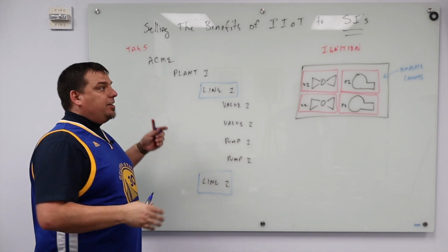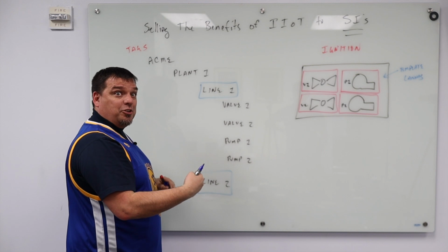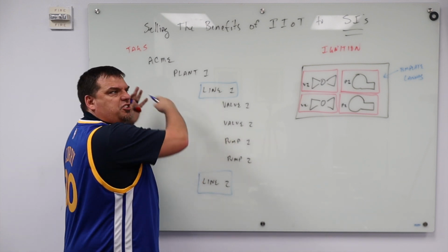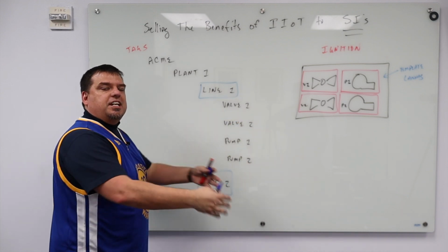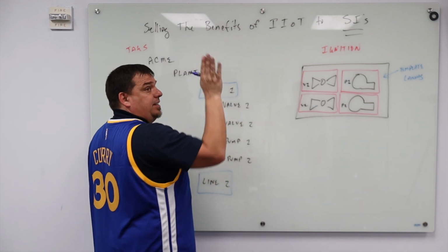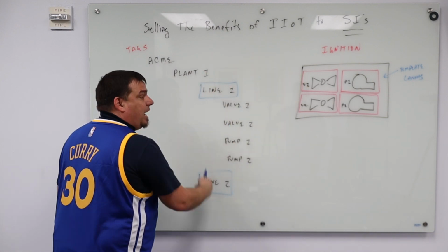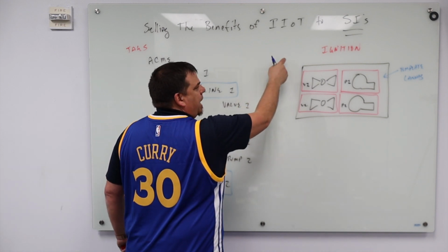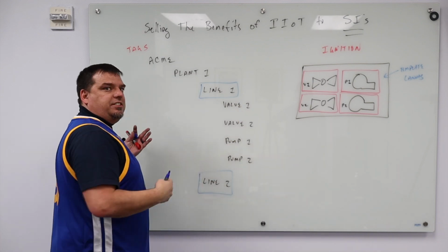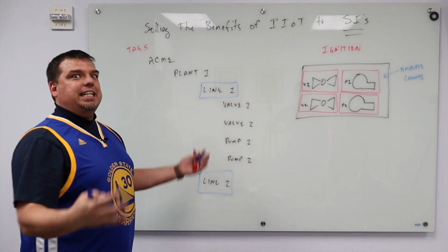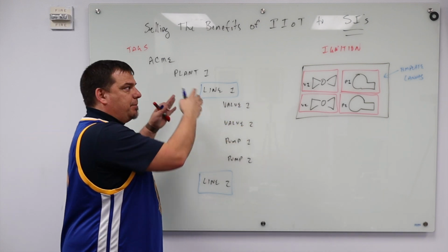In the old days, you had to have your OPC server point to this PLC. You have to build all your tags in your OPC server, and then they'll be here. There's a ton of engineering that goes into just getting the line and all the tags in. What MQTT does is it takes all that away. Here's the other thing. In the old way, your screens have to know what all the tags are that exist already. How many lines do you already have? Because you're going to statically bind, if this is an indirect window, you're going to statically put in what the lines are. What MQTT allows us to do is build the window fully dynamic. That is, if the line exists, therefore it has a visualization, and I'm going to explain that here.